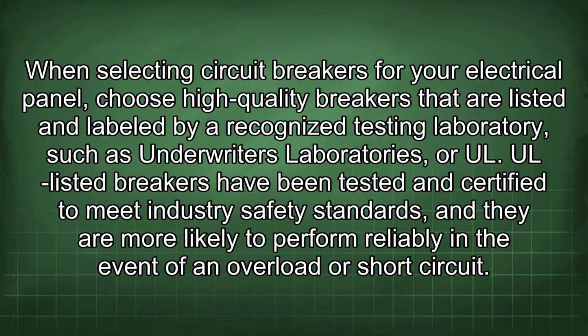When selecting circuit breakers for your electrical panel, choose high-quality breakers that are listed and labeled by a recognized testing laboratory, such as Underwriters Laboratories, or UL. UL-listed breakers have been tested and certified to meet industry safety standards, and they are more likely to perform reliably in the event of an overload or short circuit.